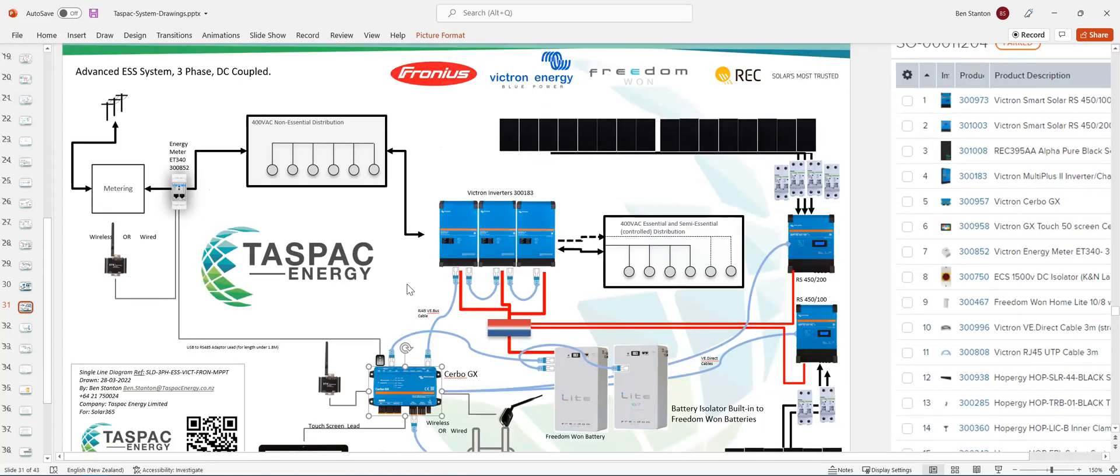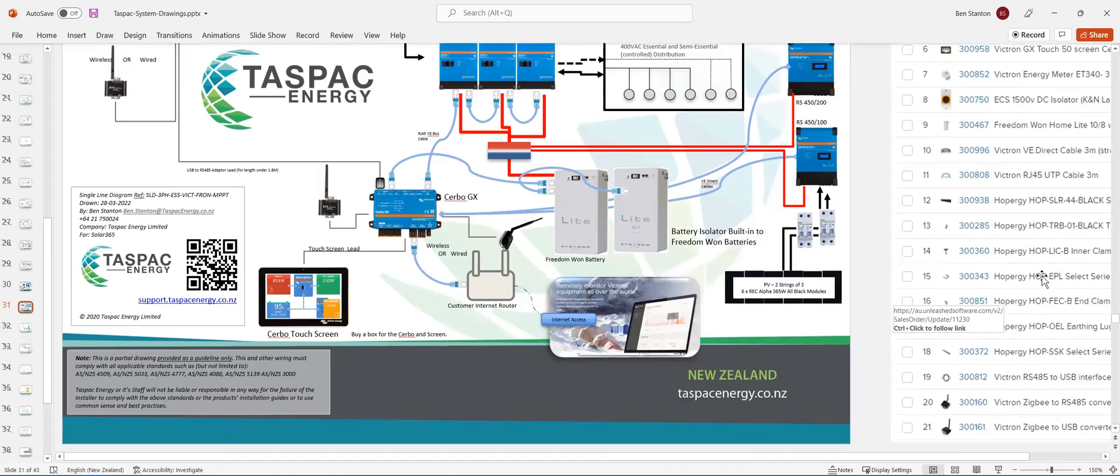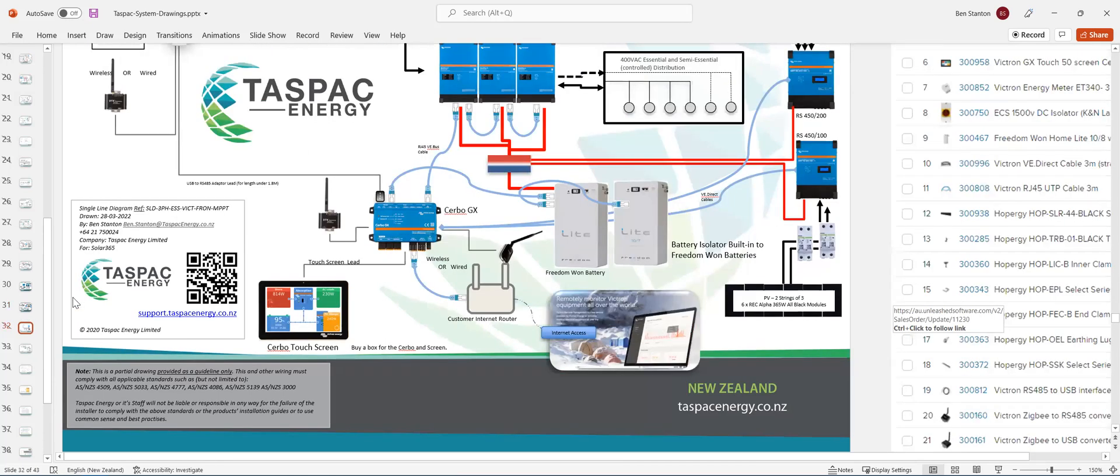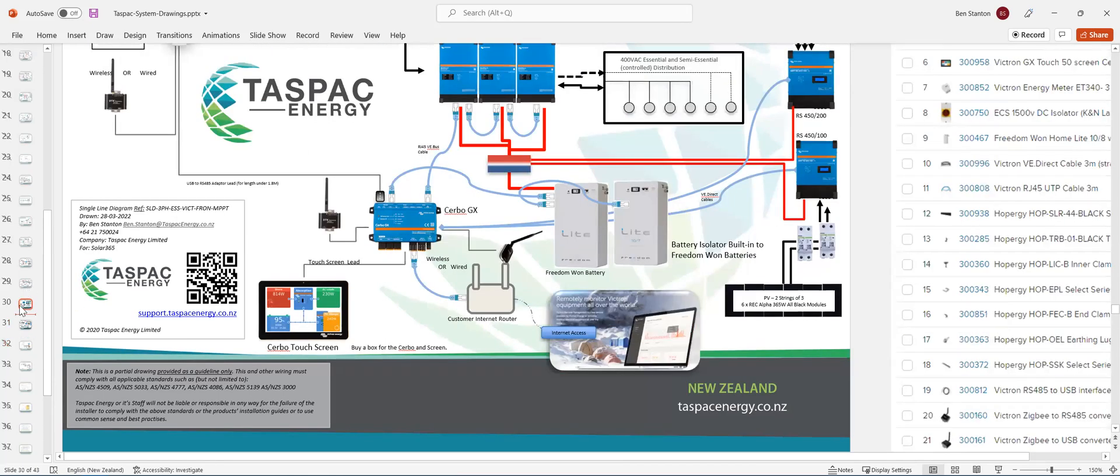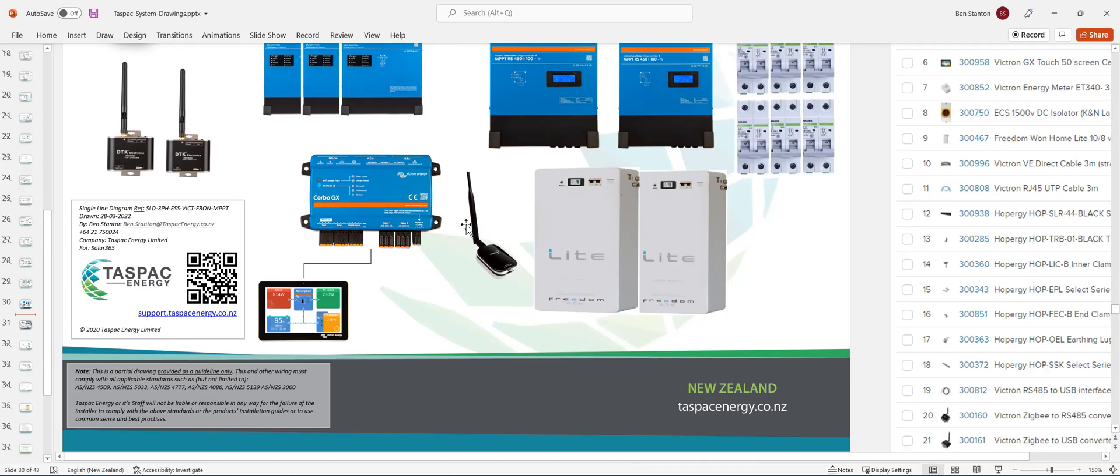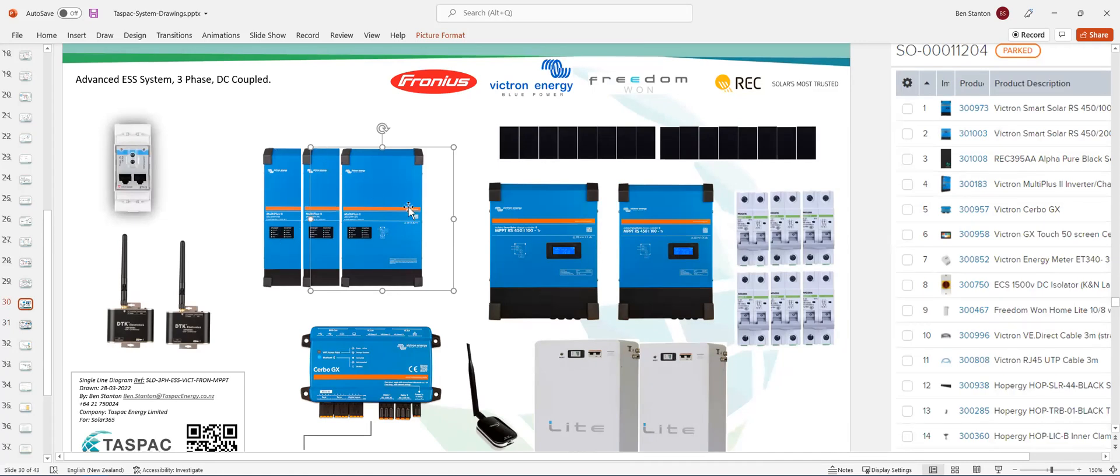Now, one thing you do need to do with a three-phase system is a little bit of a step that's required. So you're going to need to plug your laptop in, and you need a MK3 USB cable, which is a programming cable. A MK3 USB cable, which is actually a programming lead. And then you plug your laptop into the three inverters, and you set them up as a three-phase system.